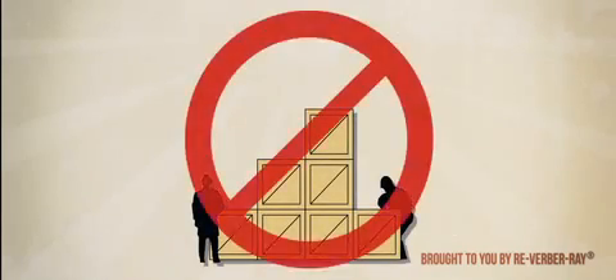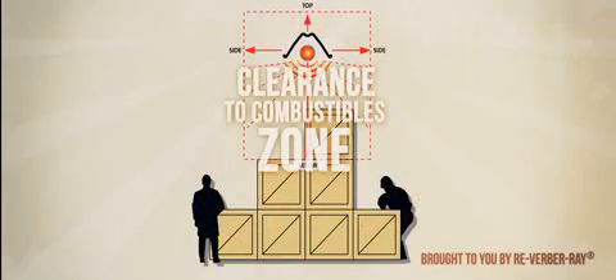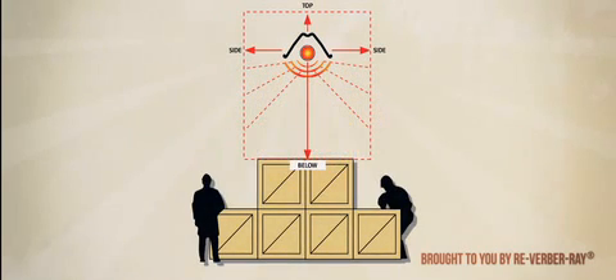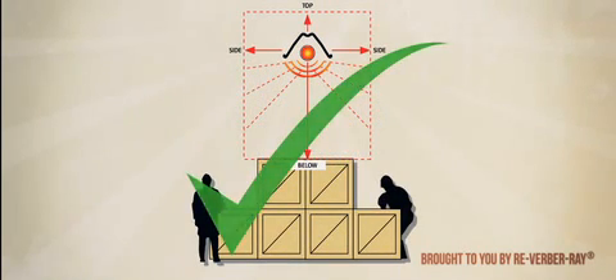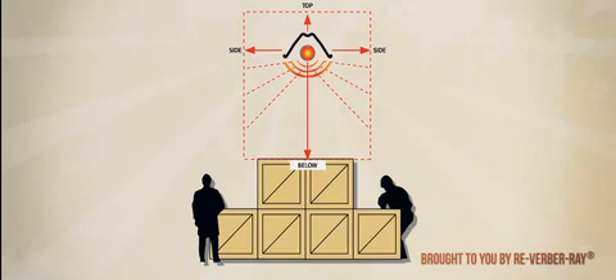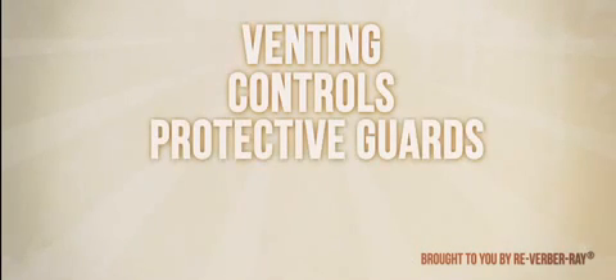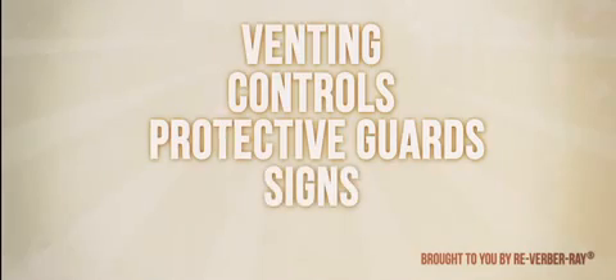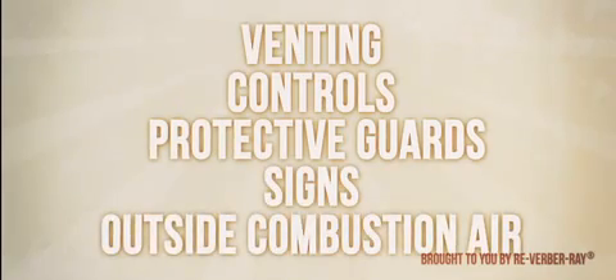Prior to finalizing heater placement, it's important to ensure that all clearance to combustibles distances will be maintained at all times, paying particular attention to storage areas, overhead doors, and car lift areas. Other related considerations include venting, controls, protective guards, signs, and the utilization of outside combustion air.